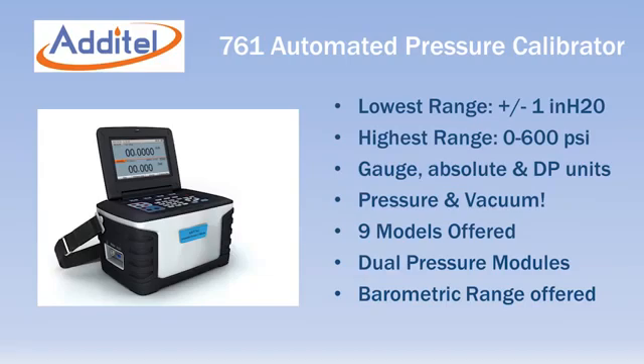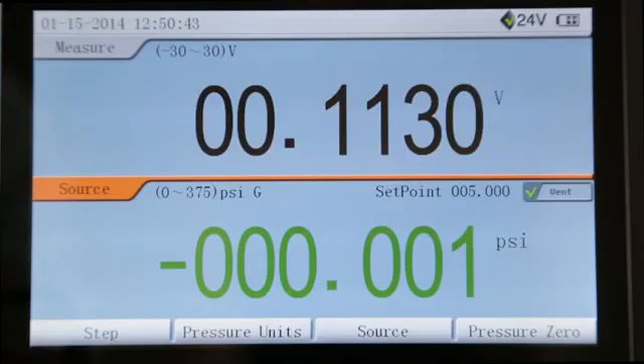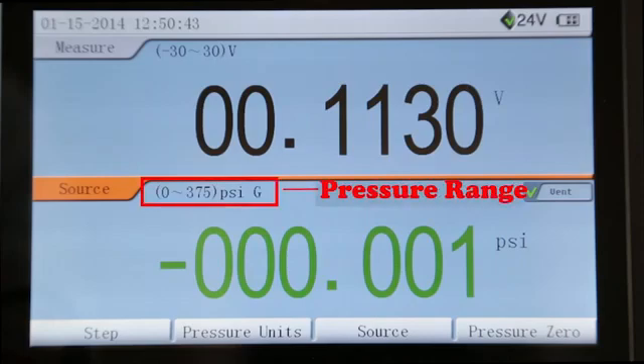The 761 is manufactured in 9 different models that cover gauge, absolute, and differential pressures and vacuum from one inch of water to 600 psi. Each 761 has two internal pressure sensors to provide accurate measurement over a wide range of pressure and vacuum.